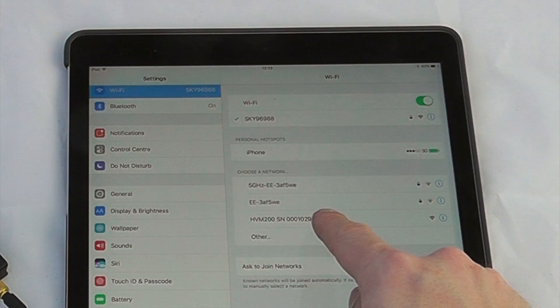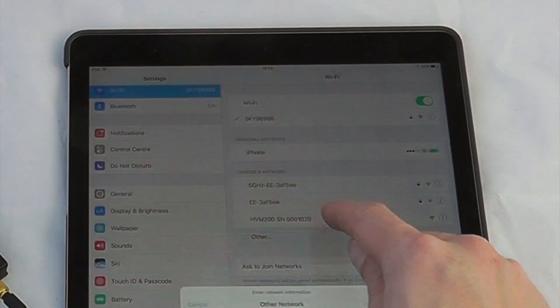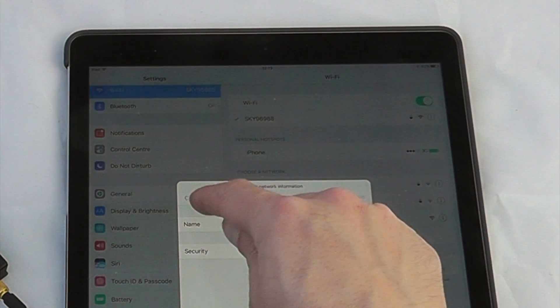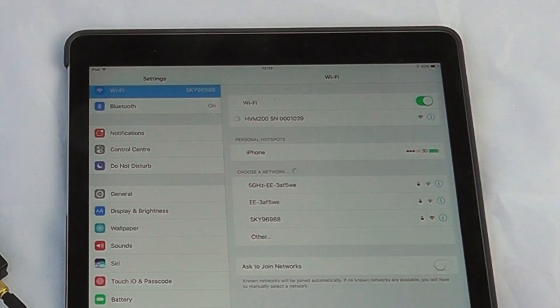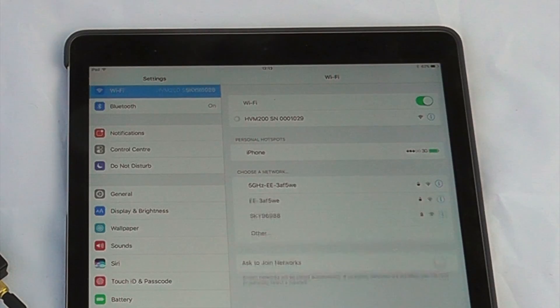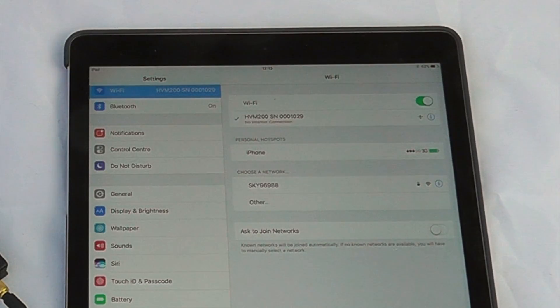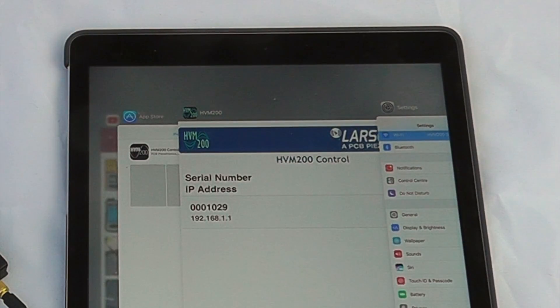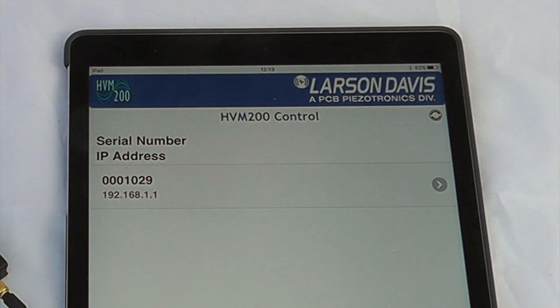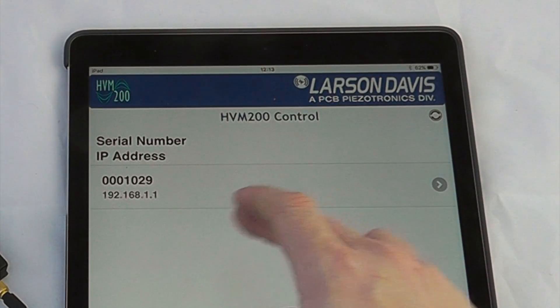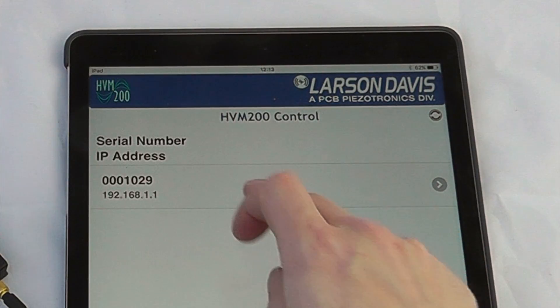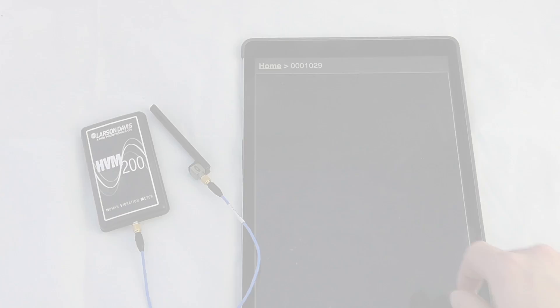I can see the HVM 200 here so I can connect to that. Select the HVM 200. My iPad will then go and have a look, and then if I open up the HVM 200 utility software, I can now see the serial number of the instrument I wish to connect with. So 0001029 is where we're looking.